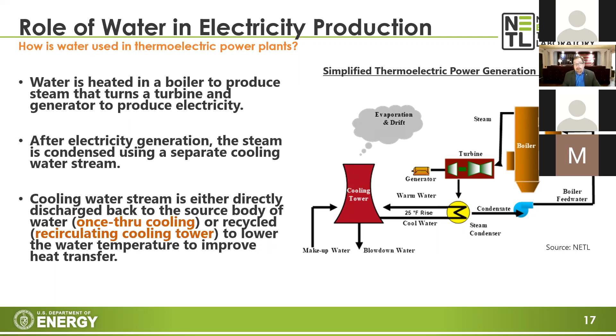Once-through has very high withdrawal comparatively, but very low or near zero water consumption, and it's relatively cost effective in the sense that after the condenser, we directly discharge back to the body of water.